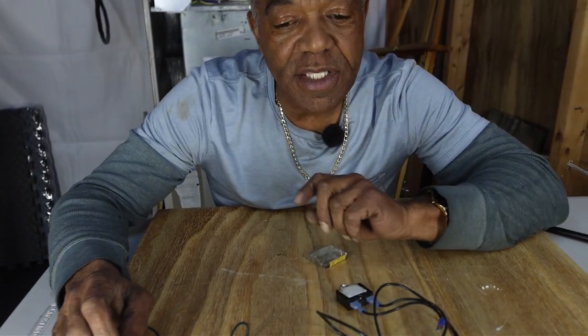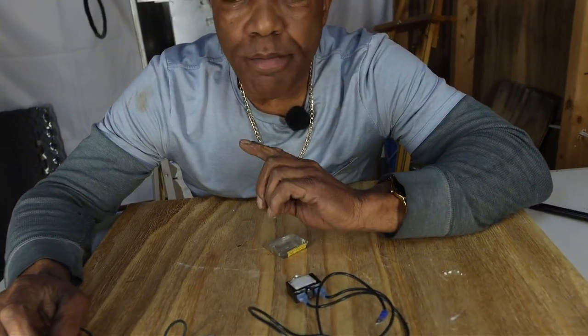Again, it's about understanding. Most of the time, I can walk up to a unit, turn it off, turn it back on, and the unit tells me what the problem is. I use things like this alligator clamp to ensure that the diagnosis that I came up with was correct. If I believe that the flame rollout switch was the problem and I jump the flame rollout switch, then the system should run. It should work. Now I have proven that my theory was correct.